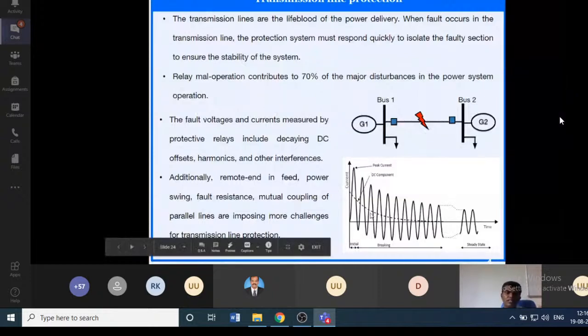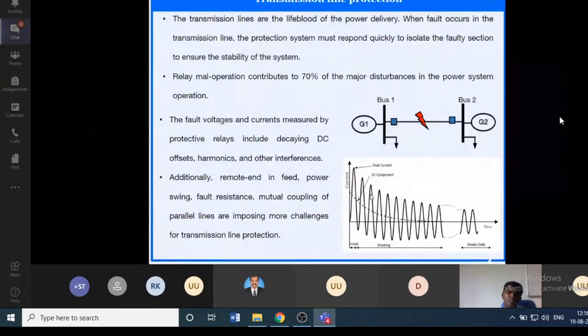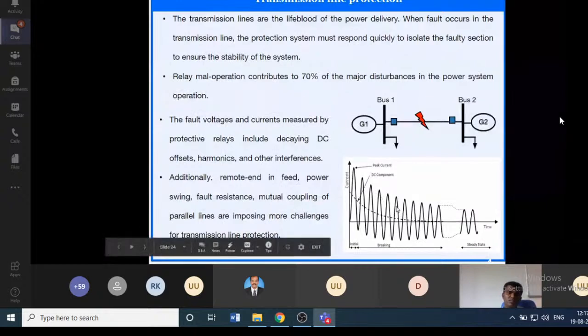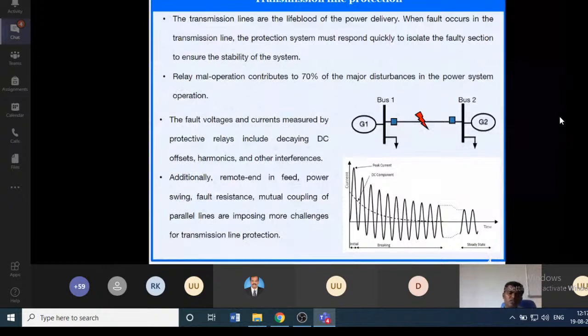Additionally, the system may have power swings, which add some challenges. When a fault occurs, the relay should respond very quickly to isolate the faulty section. Most disturbances in power systems occur due to relay maloperation, so we should go for a better protection system to avoid these disturbances. The fault currents and voltages contain a DC component, harmonics, and other interferences, so from this we need to filter out only the fundamental harmonics using transform techniques.